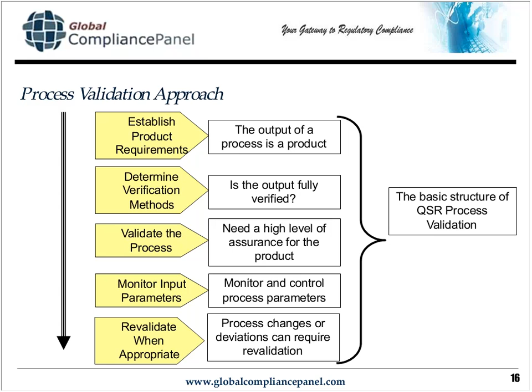This is parallel: I have to validate any process for production and service provision—that's the term in 13485—where the resulting output cannot be verified by subsequent monitoring and measurement. In other words, when I can't check the output of the process through monitoring and measurement—in QSR we called it inspection and test—then I have to validate the process.